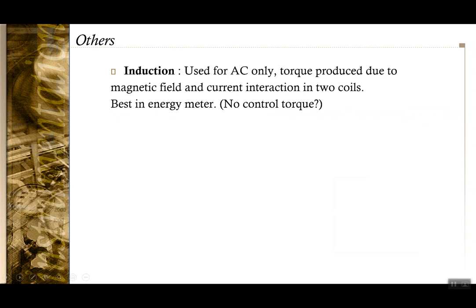The induction type instrument is generally used only for AC measurement, where torque is produced due to interaction of fields and currents in two different coils. They are best used as energy meters and are integrating-type instruments — you're interested in the integral of the measurement, not the instantaneous value. The number of revolutions gives energy output, and they can also measure power, though utility in that case is limited.